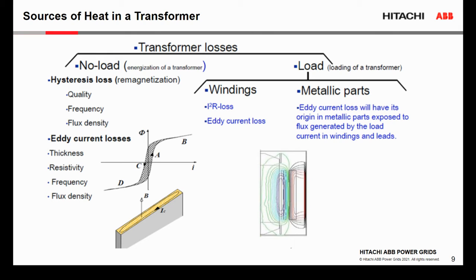The other component, which is much higher, usually 3-5 times higher than the no load losses, is the load losses. The load losses are generated in the windings. The first component of the winding losses is the I2R component, or sometimes we call it ohmic losses. Another component is the eddy losses, and usually eddy losses in the winding are 10 to 15% of the ohmic losses. Also, in metallic parts like the clamping structure, the tank, the turrets or cover, we generate other eddy losses. The load current generates the flux density, and with that we induce eddy current in the metal parts, and we generate losses in those metal parts.